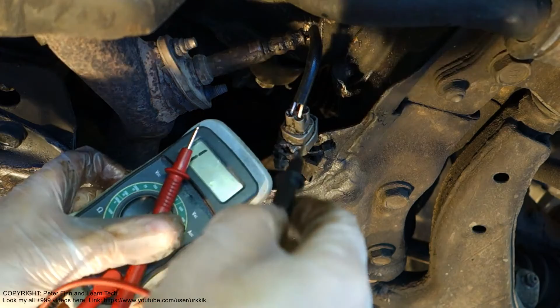Next, with the cable on and the oxygen sensor connected, I will measure the real oxygen amounts. There are two cables that measure this oxygen percentage, and I insert my probe. There's a sharp spike, and I press it a little through this plastic white cover. Inside, as we can see, there is copper, and I need to press my spike enough that it goes inside this area.